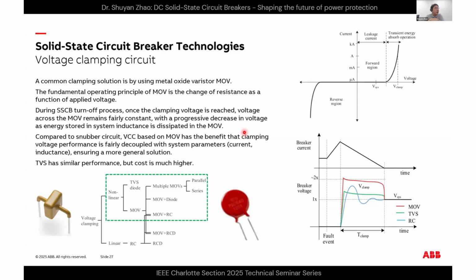For mechanical breakers, based on my understanding, the existing standard that regulates lifetime says it should be capable of operating for ultimate short circuit fault at least a few times, then it needs to be replaced or maintained. For nominal interruption operation, it requires proper operation for thousands of operations. That's relatively limited compared to solid state - we're pretty flexible to design for lifetime requirements.